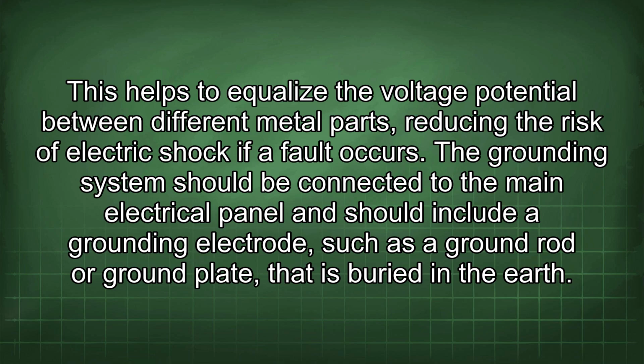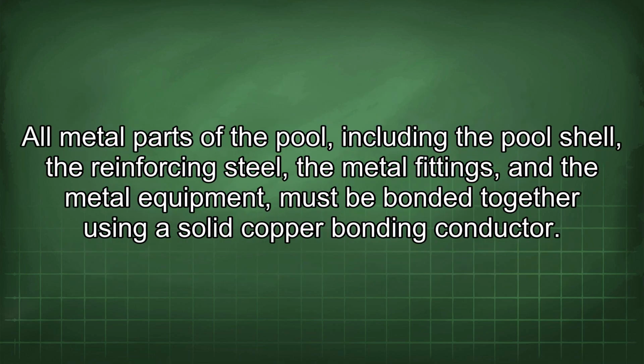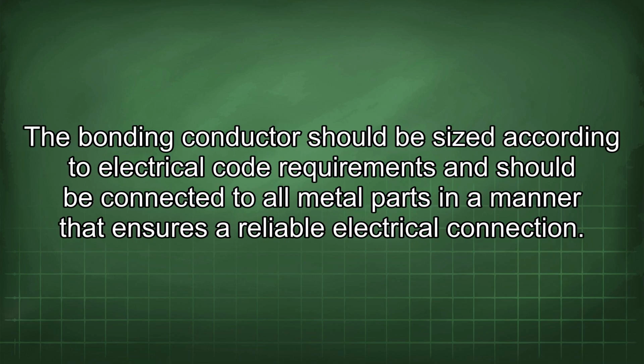The grounding system should be connected to the main electrical panel and should include a grounding electrode, such as a ground rod or ground plate, that is buried in the earth. All metal parts of the pool, including the pool shell, the reinforcing steel, the metal fittings, and the metal equipment, must be bonded together using a solid copper bonding conductor. The bonding conductor should be sized according to electrical code requirements and should be connected to all metal parts in a manner that ensures a reliable electrical connection.